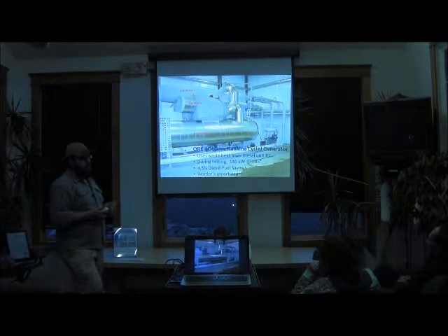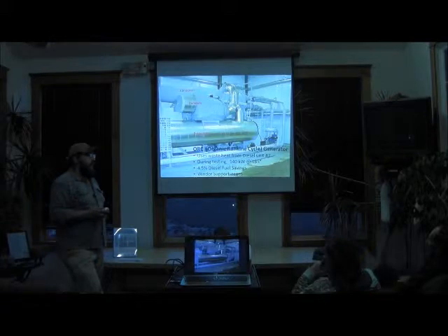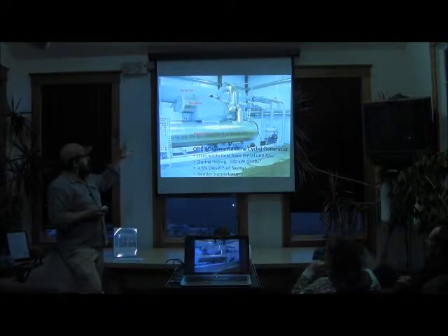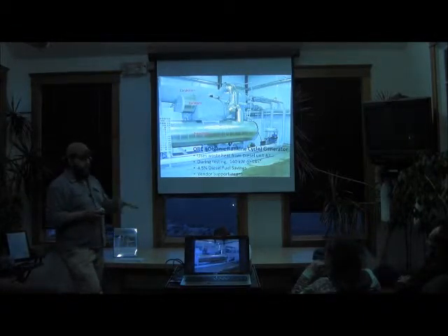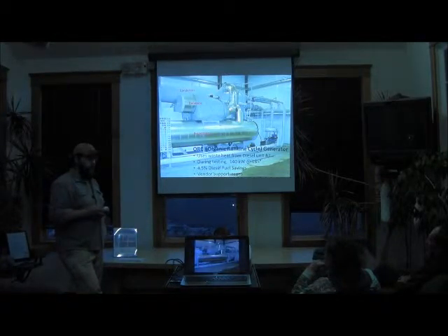And you can't send every single generator through there, it's only the one? Right now, we're looking at connecting the other units. The problem is the temperature of the diesel coolant is about 190 degrees, which is right at the bottom end for these heat recovery machines. So we wanted to put it on our big unit first, since it produces the most heat, and make sure it works before we did all the plumbing to connect all of them.